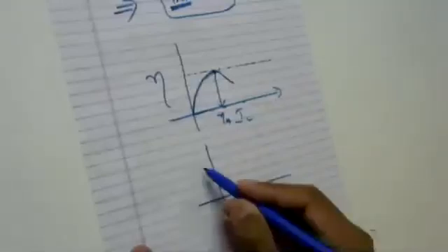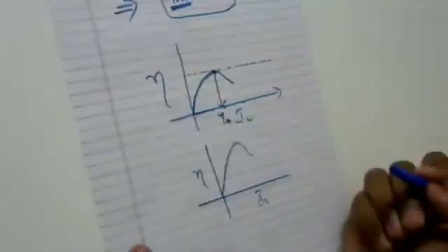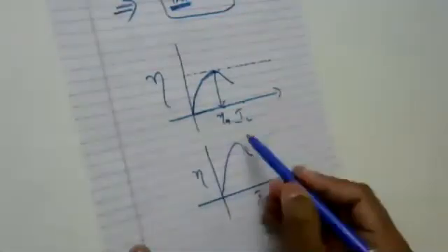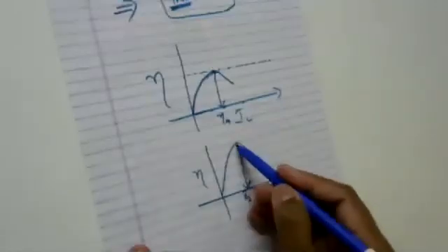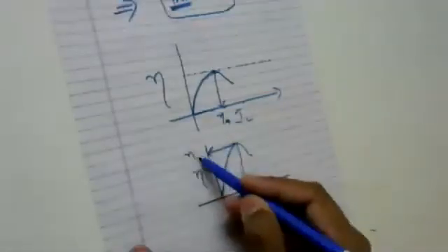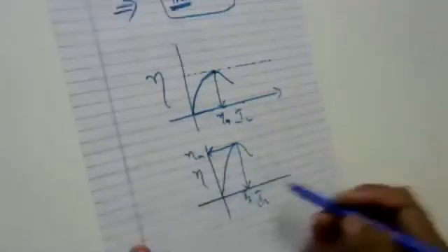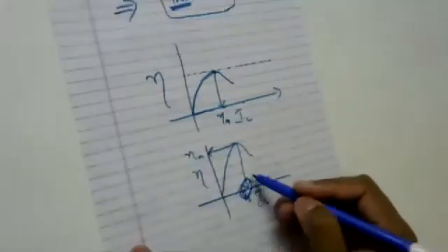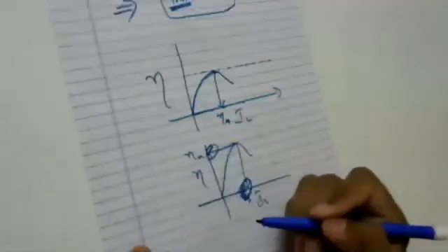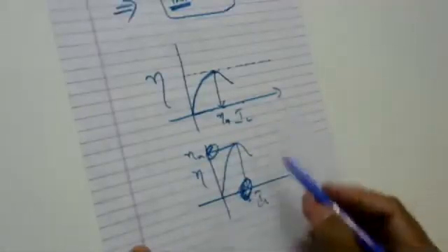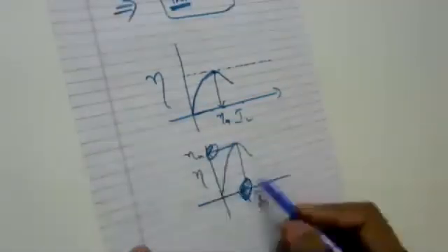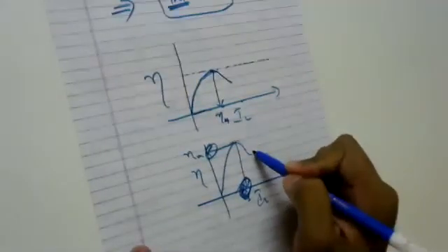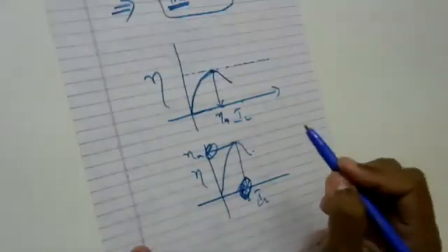For any electrical machine, when you plot a graph of load current versus efficiency, you get a graph somewhat like this. This point is the maximum efficiency point. At this maximum load current, you get the maximum efficiency, eta max. If you load your transformer beyond this point, then efficiency is going to drop. Is it clear to you?